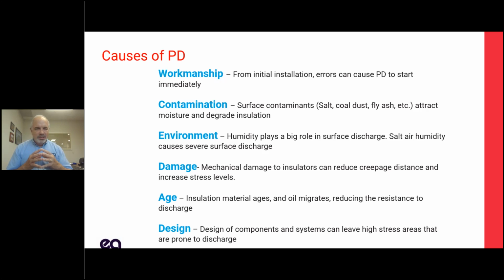And the last thing is design. The design of the components, whether they're designed so that they're hard to install and installation errors occur, or because they're just designed so that there are some high stress areas. It happens. We've seen it in switchgear, we've seen it in cable terminations, we've seen it in overhead insulators. Poor design does exist from time to time. It's unlikely, but it does happen.